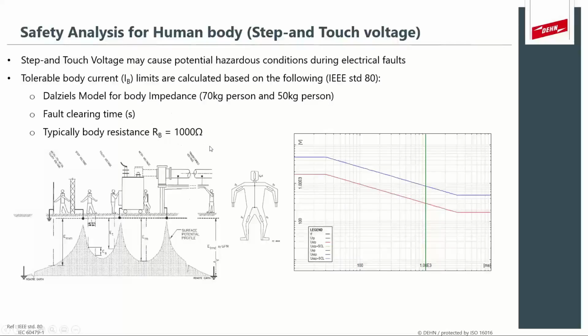So that's a good basis to start the calculation. Now, the human body resistance also changes depending on the weight of the human in IEEE Standard 80. The idea is to limit the body current as much as we can as it flows. In this calculation, as I said, the body impedance stays at 1,000 ohm. We know what the current limit can be, so we have to ensure that the voltage stays low enough so that we don't achieve that current in conjunction with that body resistance. Now, XGSLab calculates these step and touch voltage limits for you.